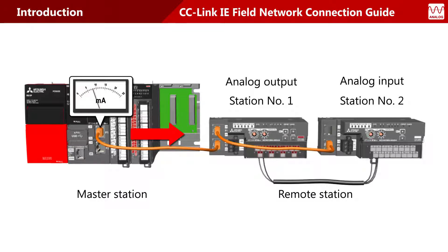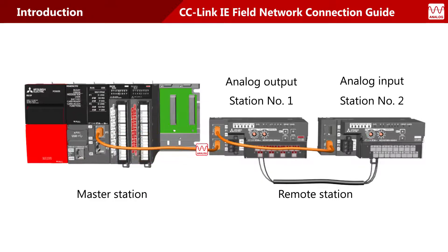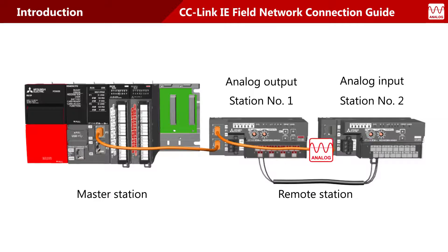When the master station sends an instruction to station number 1 to output an analog signal, the specified value is sent to the analog output module via the network. The analog output module sends the analog signal to the analog input module, and the analog input module returns the input value to the master station.